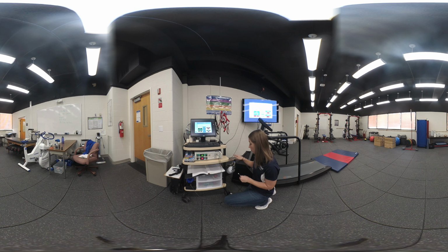one tank. So to be able to assess the gas that's in the tank, I'm going to take my tube and I'm going to connect it to the port that says gas cal out. So once that's connected, the next thing I need to do is open up my gas tank. So when I click continue, it's going to say, warning, you need to open your gas tank on the computer screen. So it's lefty-loosey, righty-tighty to open the tank. So I'm going to open that using the valve, and then I have to open the part that controls my flow rate on the side.